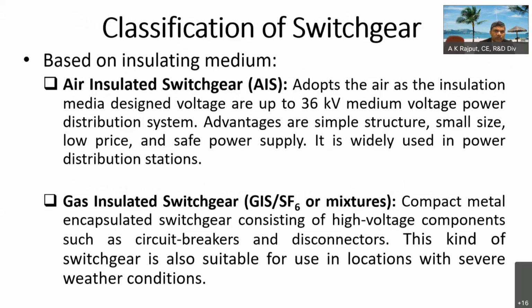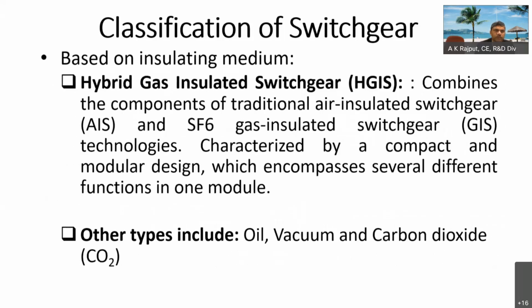So there are various types of classification. One is the air insulated switchgear, of course up to a 36 kV or 33 kV system, nominal voltage 36 kV. It requires somewhat higher space, but when the technology was not there, we had to do with that only. Then came the GIS. It offers compactness and the space requirement got reduced. Of course, the cost became slightly higher as compared to the AIS, but the savings to the utility occurred in the form of lesser space requirement.